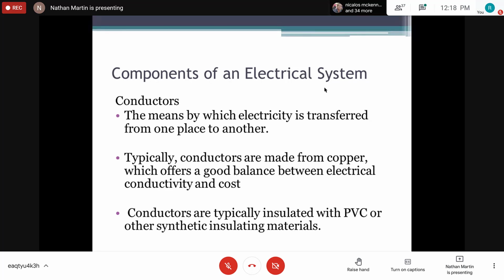All right, guys. So we said that the conductors are typically made from conductor aluminum, right? When we're talking about overhead cables, we talk about mainly aluminum type cables. Now, these cables are designed to facilitate weather conditions and high tension conditions, meaning that under stress, because a lot of time they'll be running from the distribution pole to a stanchion that is on the consumer's house.